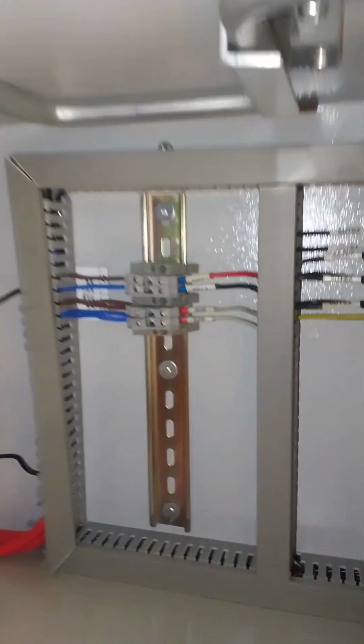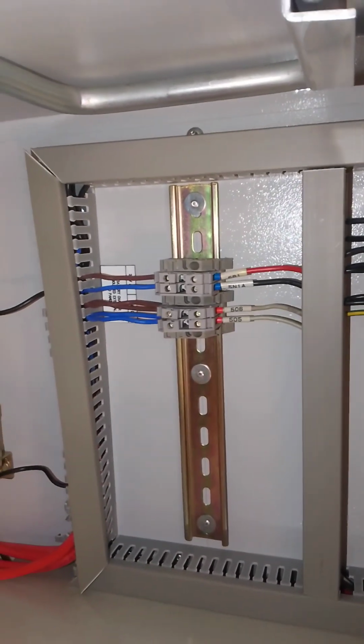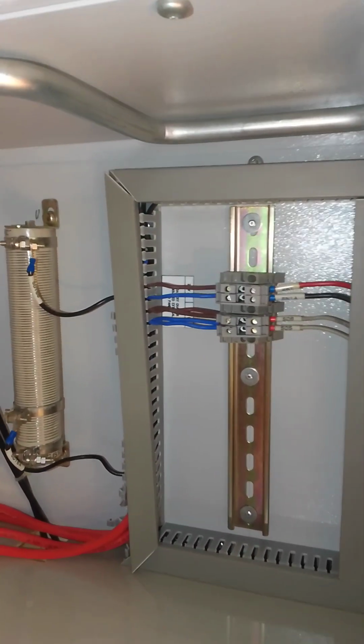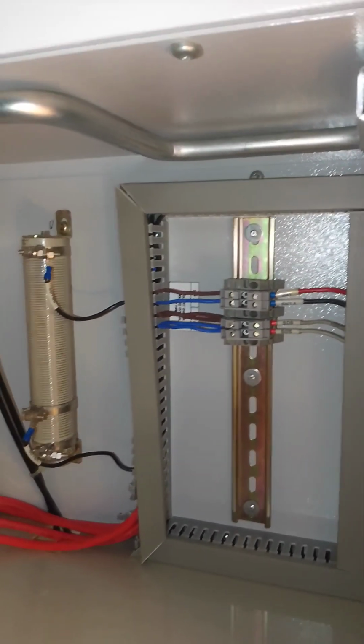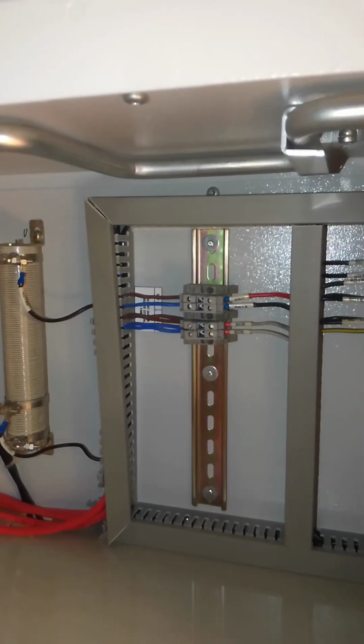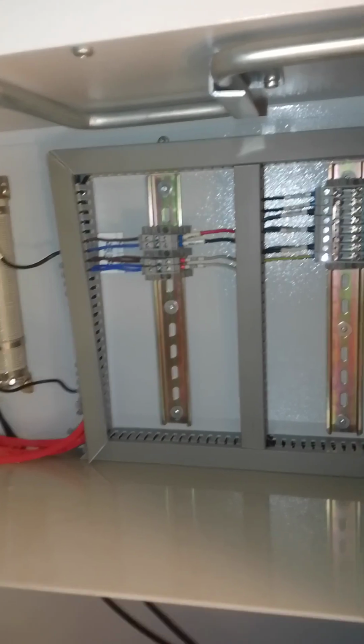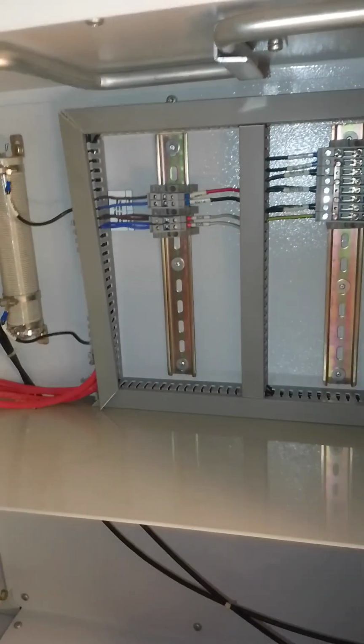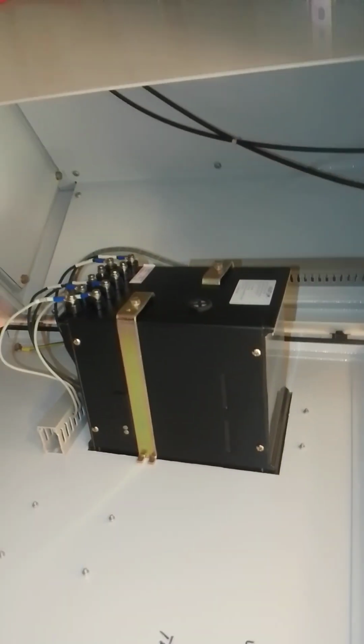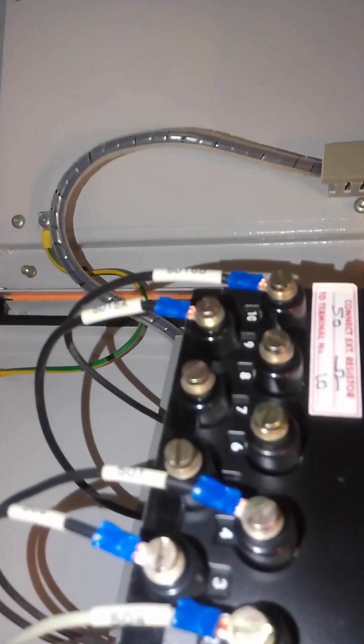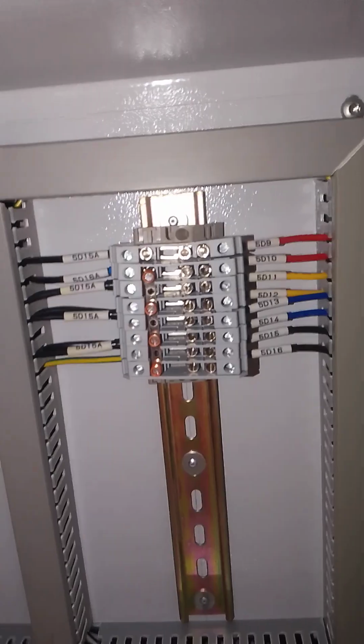If you can see, our resistor is connected with the 2 power in and out to control our generator and also our supply company power if it has a problem. This is how the relay looks inside. These are the connections. These connections comes from here. You can see these cables comes here, and also these cables also are connected to this ACB.